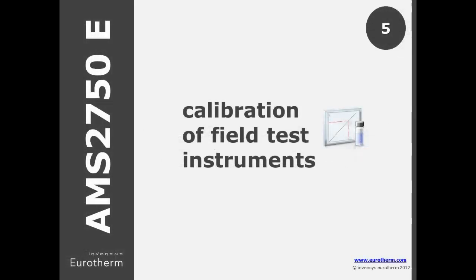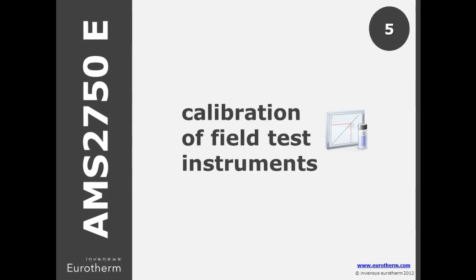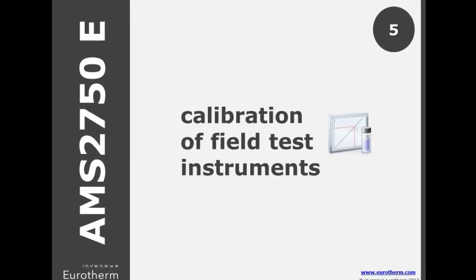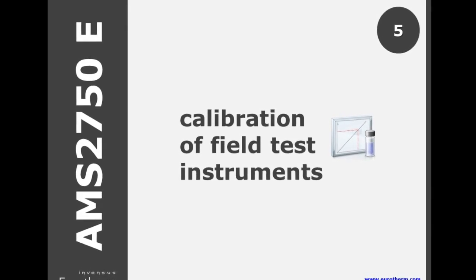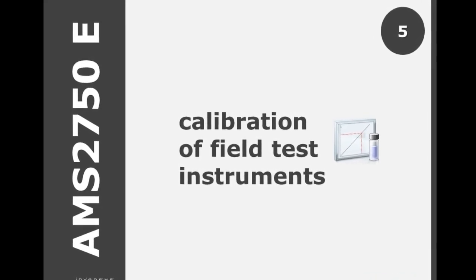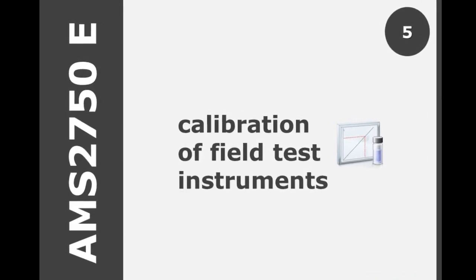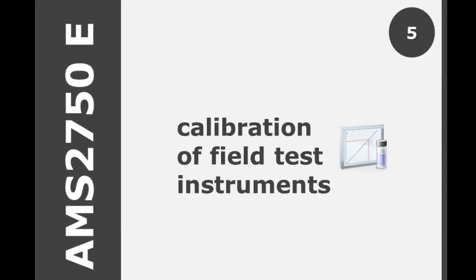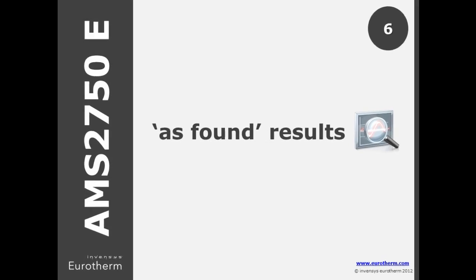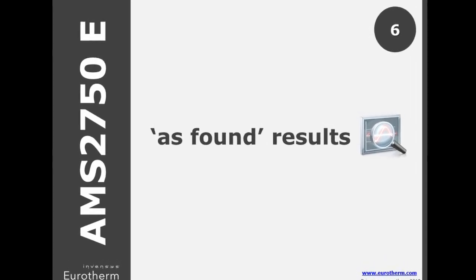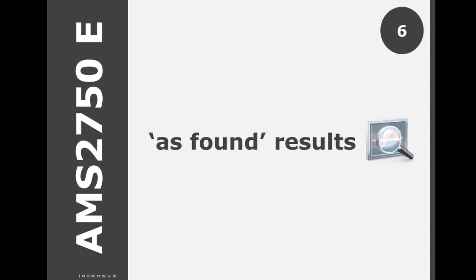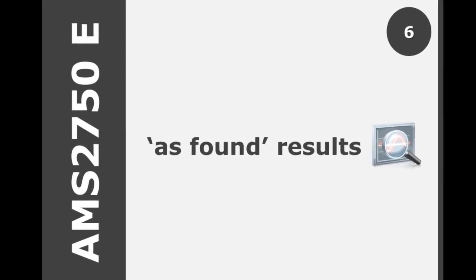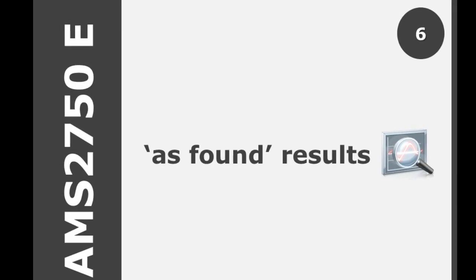For calibration of test instruments, in D this stated a minimum of 3 points, min, mid and max. In E this has now increased to 6 simulated inputs, minimum, maximum and 4 points spread equally across the working temperature range. In E, there is a greater emphasis to record the as-found calibration details, as well as recording the as-left. It is then easy to view the drift characteristics of your controller or recorder.